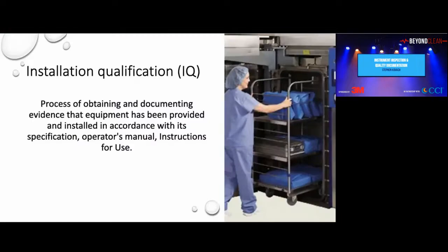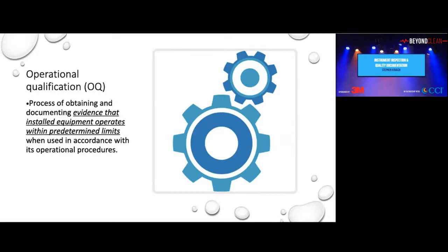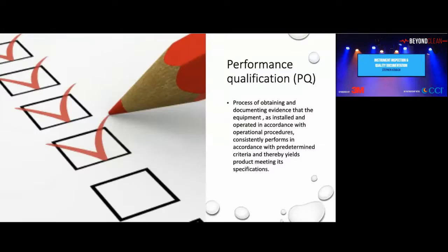And there are three terms: the IQ, the installation qualification, the process of obtaining and documenting evidence that equipment has been provided and installed in accordance with its specification, its operator's manual, its instructions for use. Then the OQ process. It's a process of obtaining and documenting evidence that the installed equipment operates within the predetermined limits when used in accordance with its operational procedure.